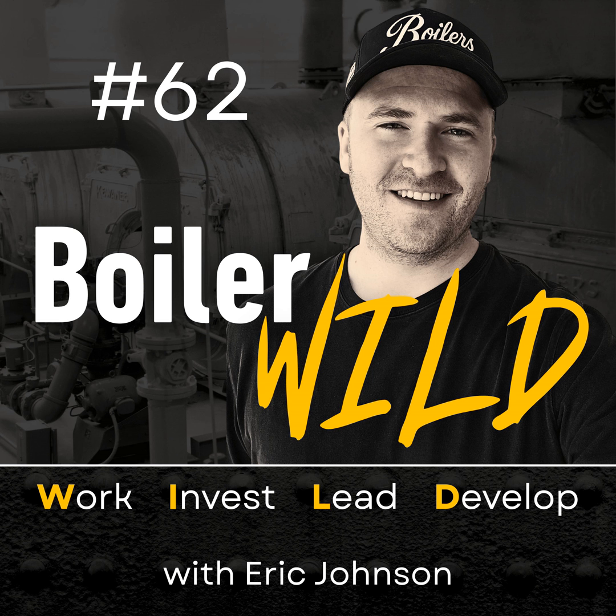So, picture this. Let's set the stage. Customer calls, hey, boiler 1 had 2 pilot flame failures last night, but it's running. Can you schedule somebody out here as soon as possible? Not a huge deal. It's running, but it'll fail 5 to 7 times a day is what our shift people are saying. And normally it starts with, oh, it failed once, oh, it failed twice, and people will just reset it. And it seems to work all shift. Oh, all right, it was probably a fluke.